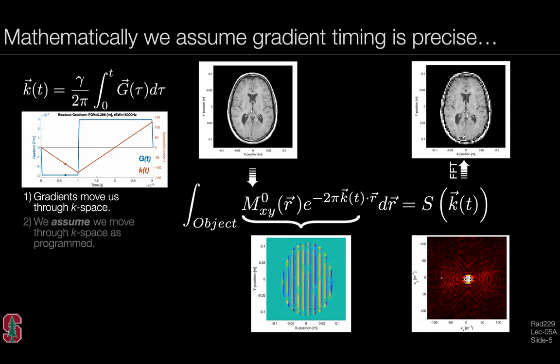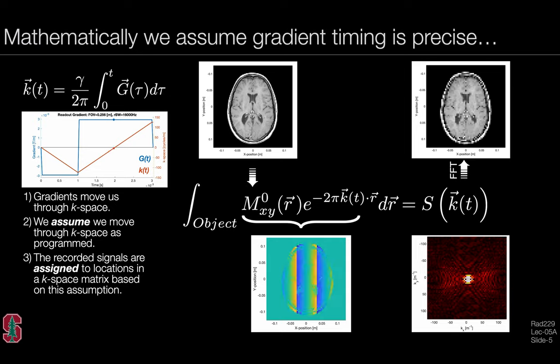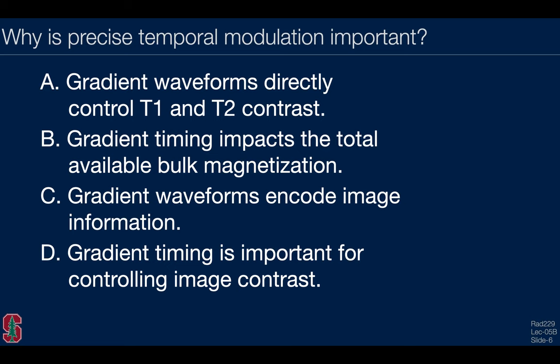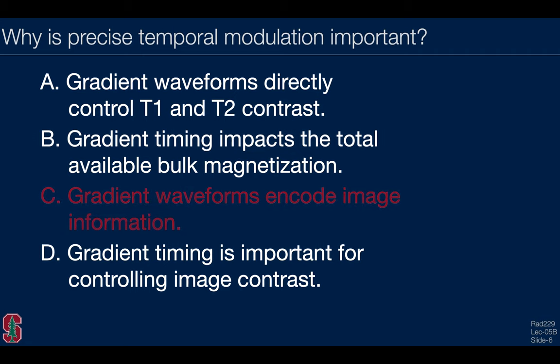Gradients move us through k-space, and we assume we move through k-space precisely as programmed. The recorded signals are assigned to locations in a k-space matrix based on this assumption. If this assumption fails, the recorded k-space is distorted relative to reality. The most important reason for precise temporal modulation is that gradient waveforms encode image information.